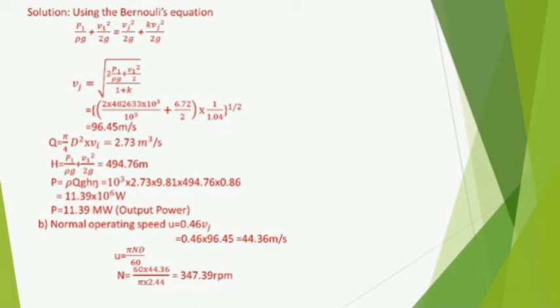For normal operating speed n: we know u/vj = 0.46, where u is the speed of the wheel and vj is jet velocity. Substituting, u = 44.36 m/s. Also, u = π n D / 60. Substituting, normal operating speed n = 60 × 44.36 / (π × 2.44) = 347.39 rpm.